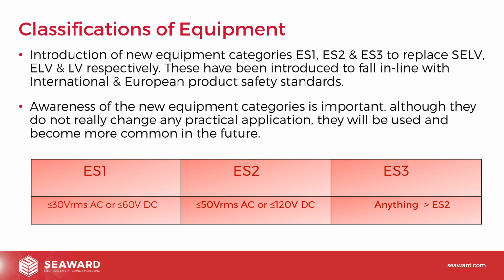ES2, anything less than 50 volts AC, 120 volts DC. So that really would have matched pretty much with your old ELV systems. Your SELV and PELV systems would probably have fitted into that voltage bracket. So that's more sensitive equipment, maybe equipment used outdoors, things like that, may fall into that ES2 category. And then ES3 really is things that are above that. So generally ES3 would be your normal low voltage equipment, your normal mains powered equipment. I'm not going to go into too much detail on these now because in reality, it won't affect what you're doing day to day that much. These are just new classifications that you need to be aware of, and we'll probably do a more detailed webinar later on to cover these.